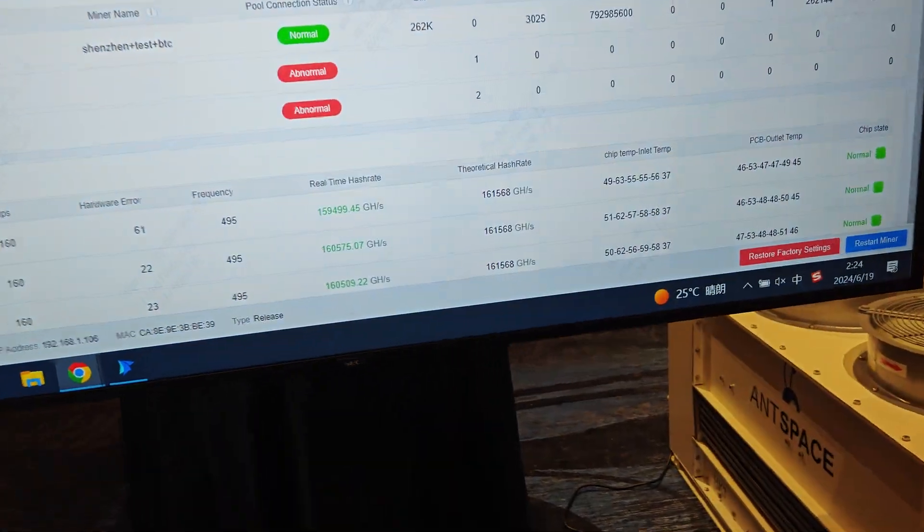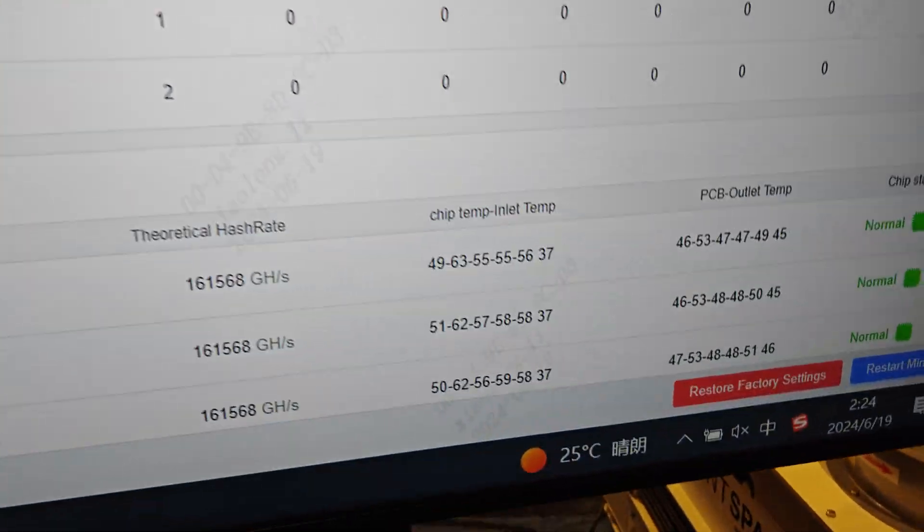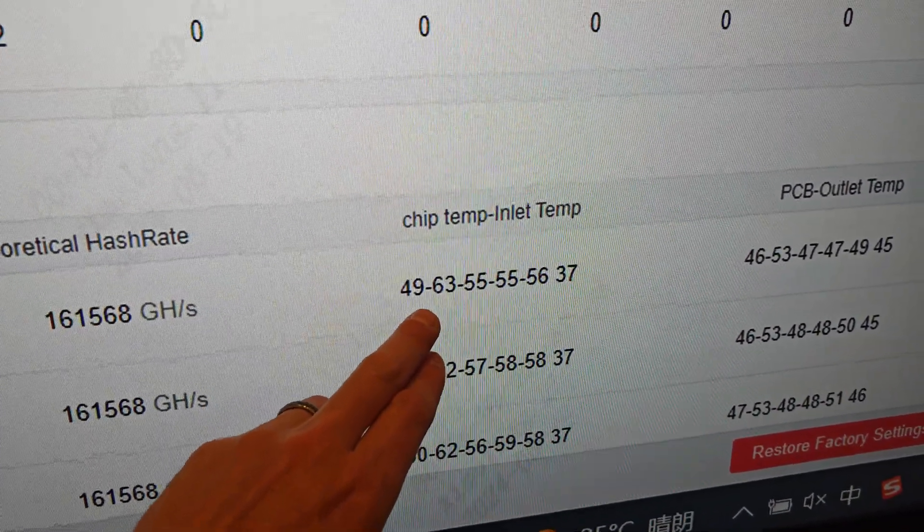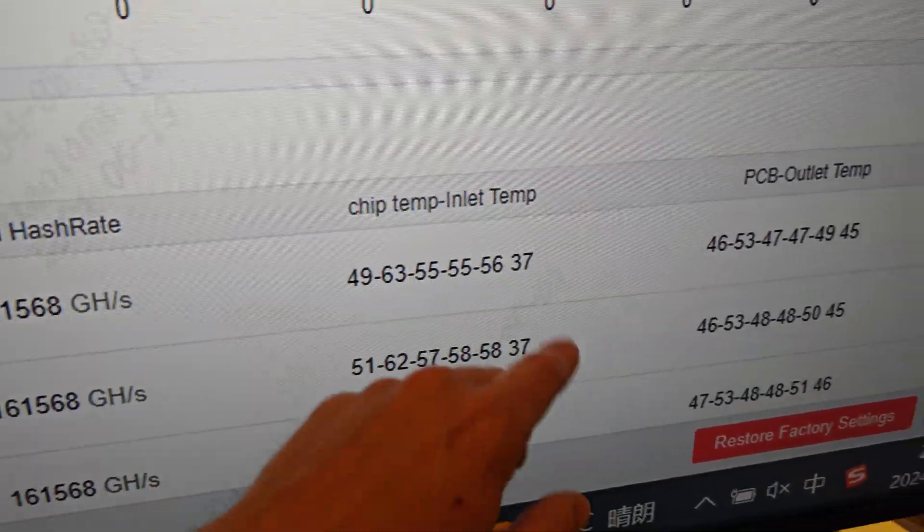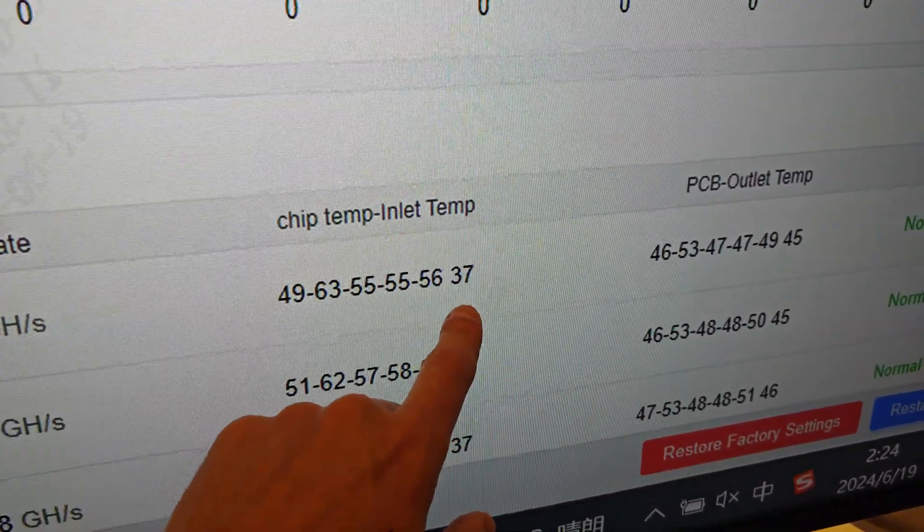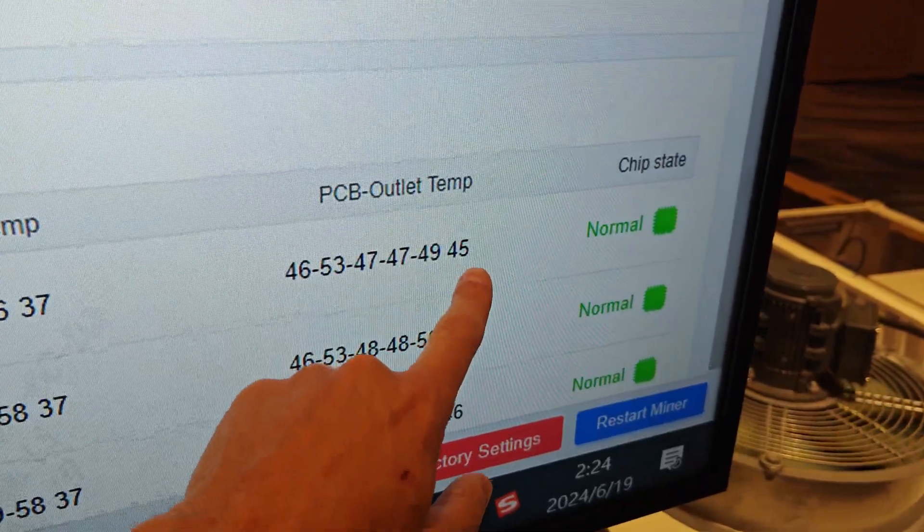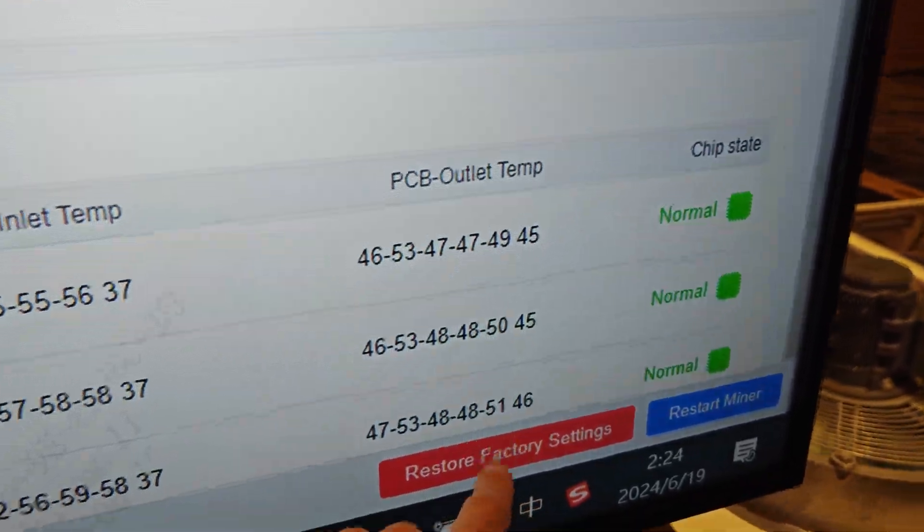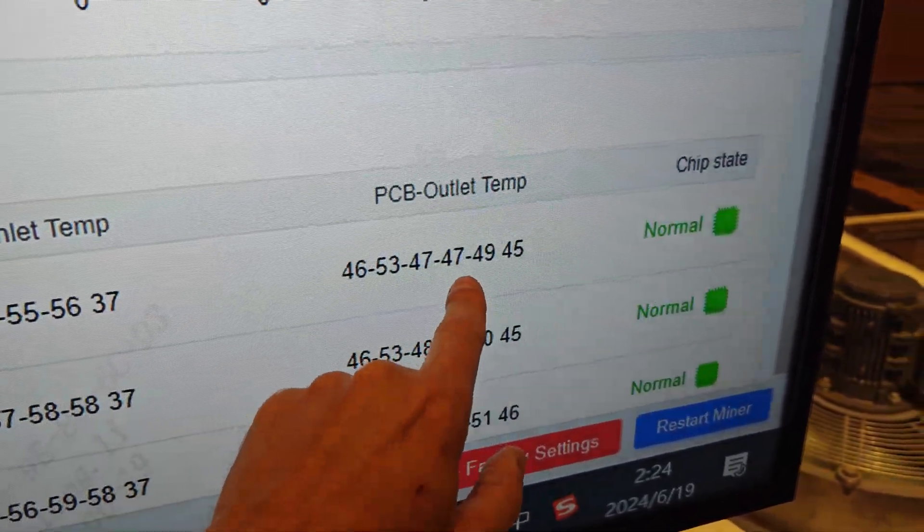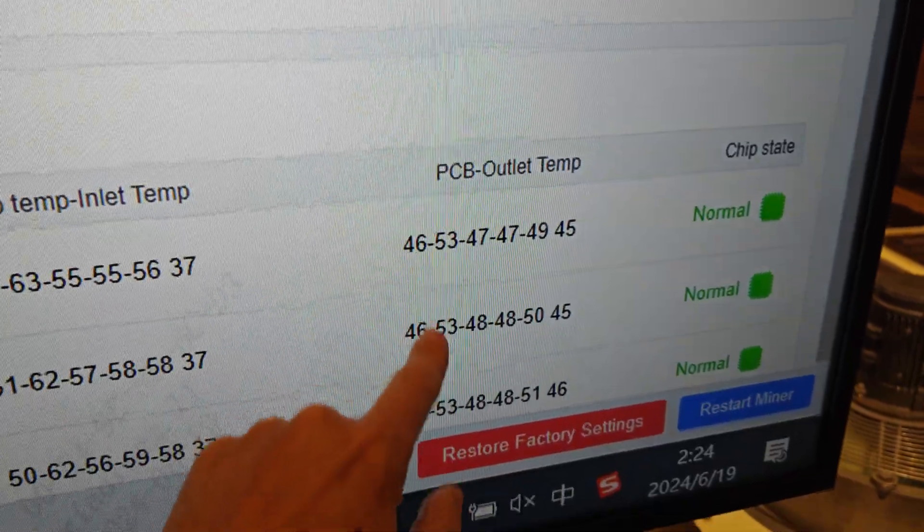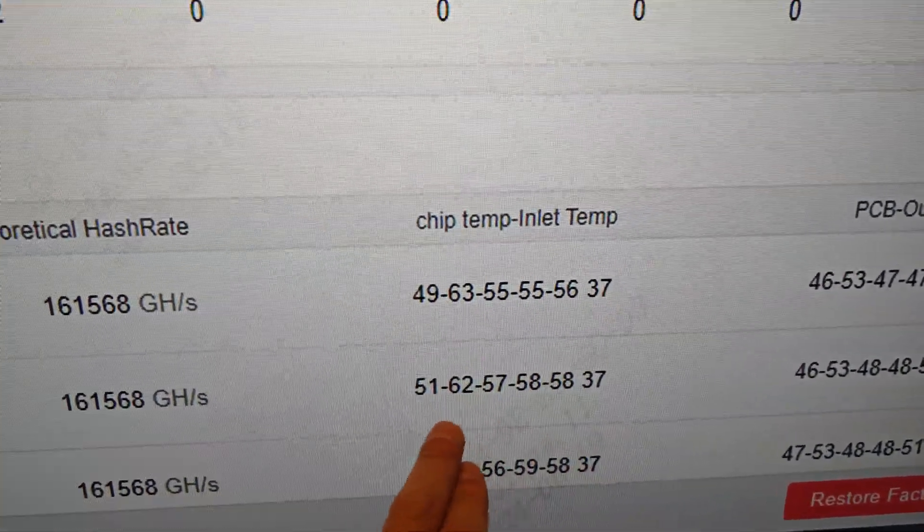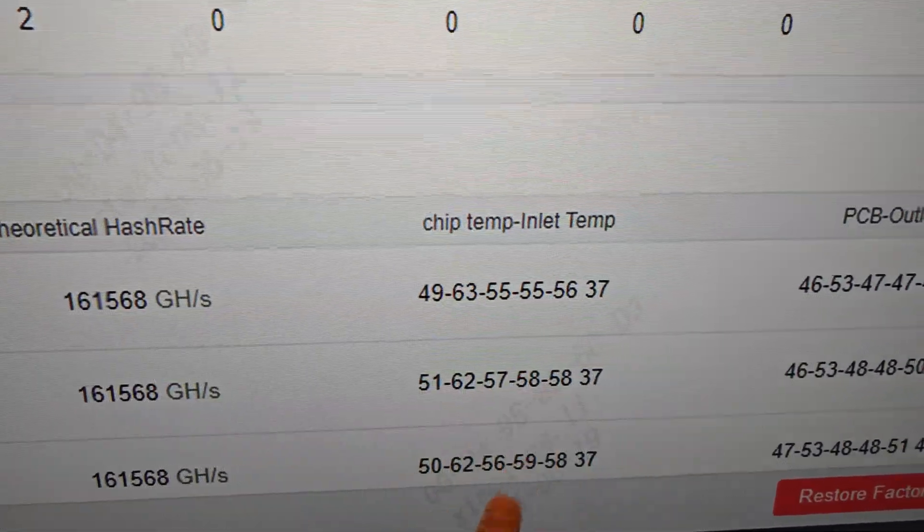But there are some changes here. You can see they added an additional temperature sensor. Now you have two, four, six temperature sensors. You got your intake temperature of the water at 37, your exhaust at 45, 45, 46, and then your temperature sensors on the PCB outlet. So these are very good numbers. You can see all of these temperature sensors are in range.